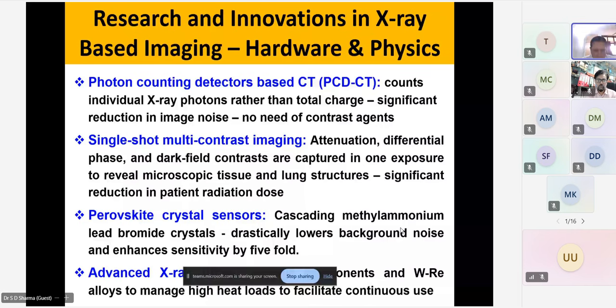The next item: if we are equipped with so many advanced systems, then definitely our X-ray machines or X-ray tubes should also be of a very advanced version, which should withstand larger load values. Because in CT scanners, we may try to take a whole body scan in one shot with such kind of available high sensitivity sensors. So considering this, a number of developments in the technology of production of X-ray tubes has also taken place. So now tungsten rhenium alloy based X-ray tubes are available, which are able to manage high heat loads and facilitate continuous use for a longer duration. So these are the major developments we have seen, and they are in place to be implemented in clinical practice.